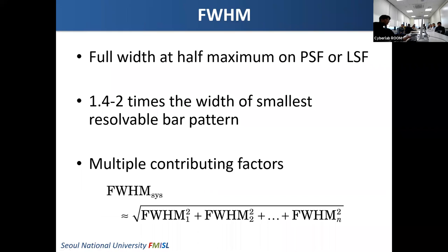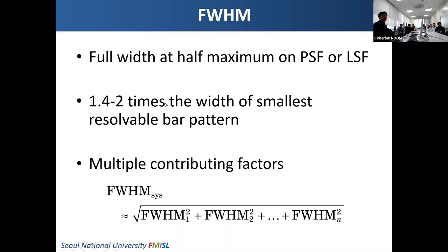For a more quantitative approach, in nuclear medicine for the assessment of spatial resolution, we usually measure the full width at half maximum, FWHM, using the point spread function or the line spread function. The FWHM is about 1.4 to 2 times the width of the smallest resolvable bar phantom.